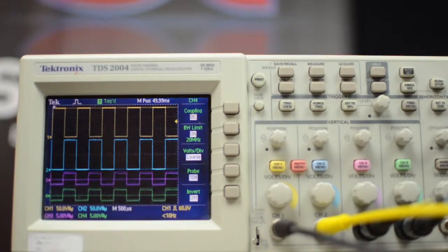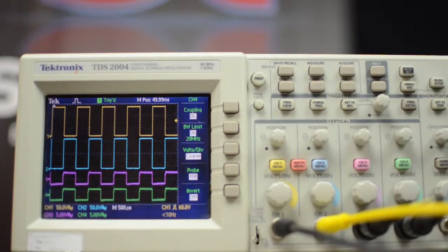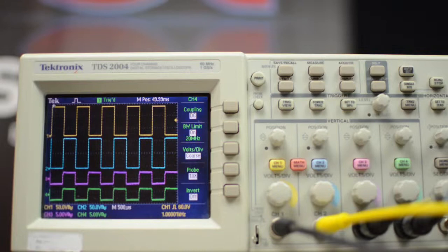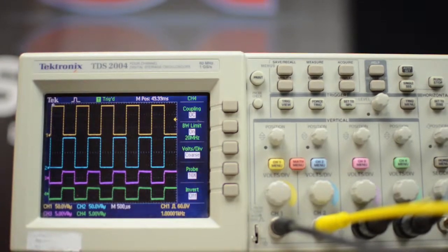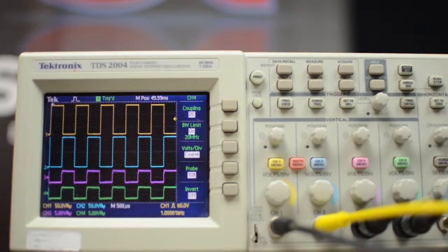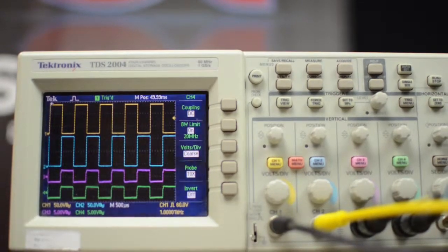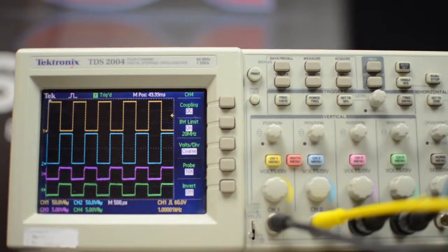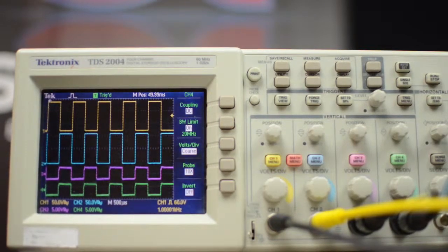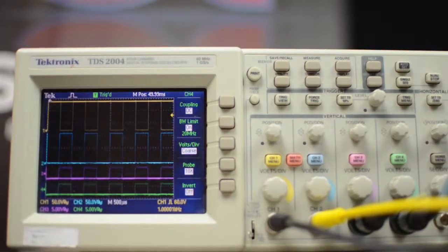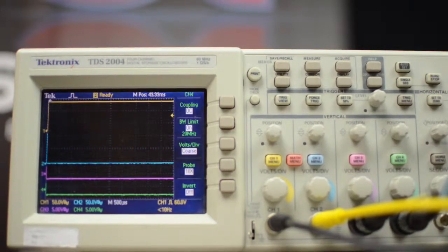If we turn on the 24V supply to these and start the batch again, we see the expected signal with the trace moving between 4mA and 16mA. Each channel may be independently set to DV or IP mode.